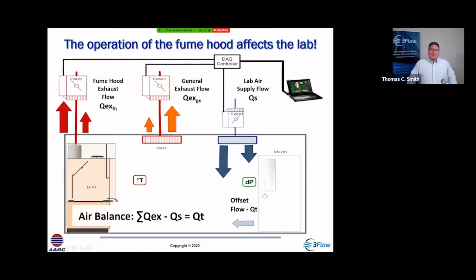Air balance here: total exhaust minus the supply equals the transfer air. So if exhaust is varying, our transfer air is going to vary. We're going to get problems with room pressurization.